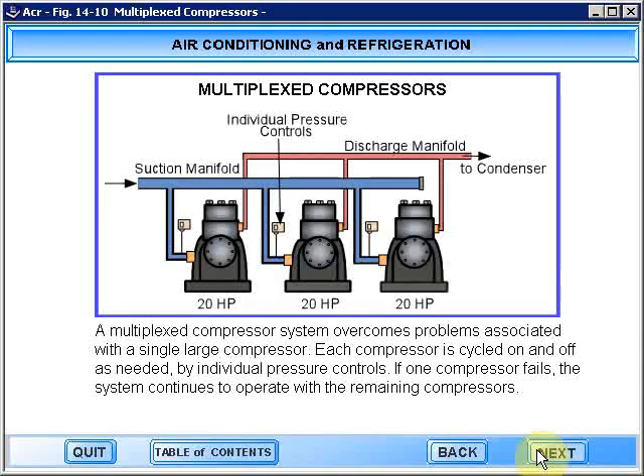A multiplex compressor system overcomes problems associated with a single large compressor. Each compressor is cycled on and off as needed by individual pressure controls. If one compressor fails, the system continues to operate with the remaining compressors.